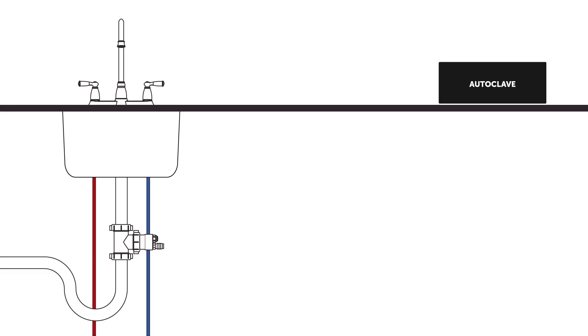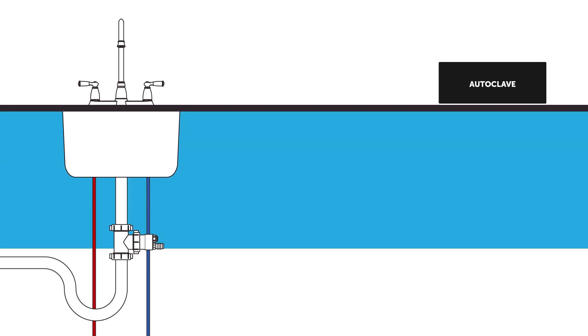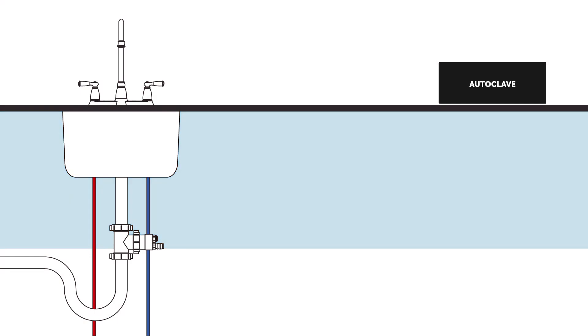The VistaCool system should be set on a hard, level surface and installed so that the top of the water tank is above the coolant overflow fitting on the drain adapter assembly and below the autoclave outlet. If the tank is below the level of the coolant overflow fitting, the system may not operate properly.